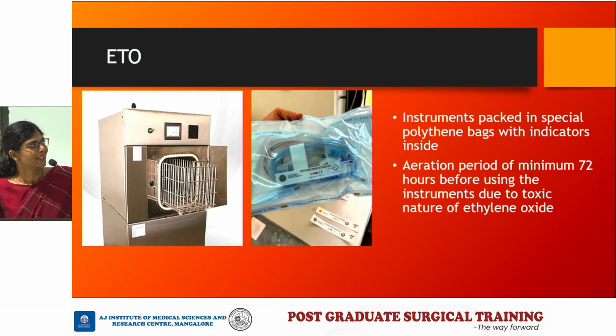Now coming to ETO, or ethylene oxide sterilization, this is done usually once a month or twice a month in most OTs. Those instruments which have wires on them, like your diathermy probes or cryoprobes, these are the instruments which can be sterilized with ETO sterilization. So the instruments are packed in special polythene bags with indicators inside, and you have to remember that this ETO gas is very toxic, so an aeration period of minimum 72 hours should be there before you use these instruments.